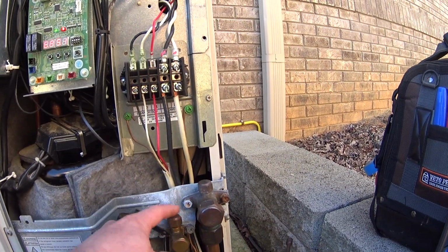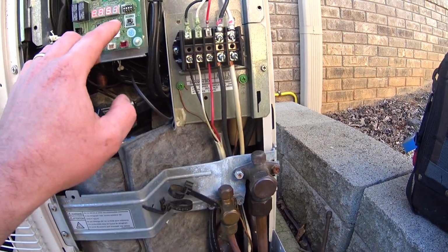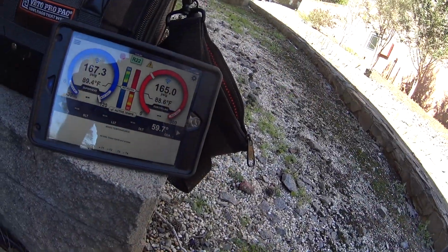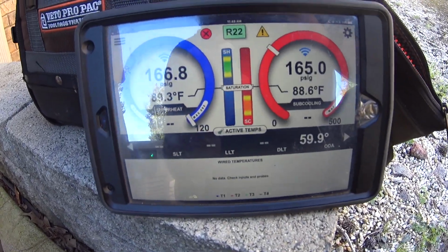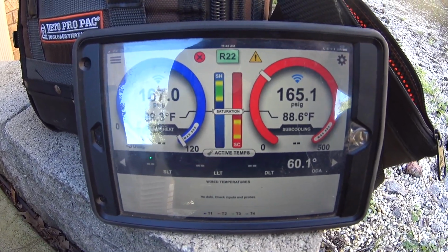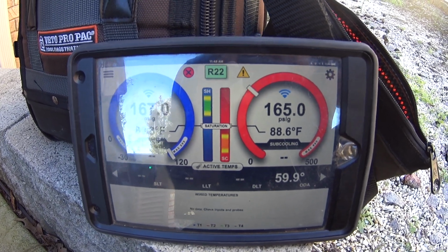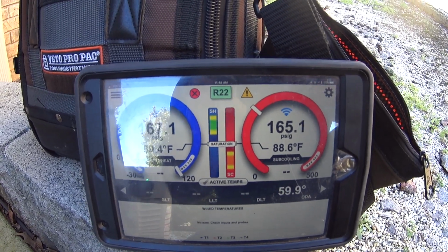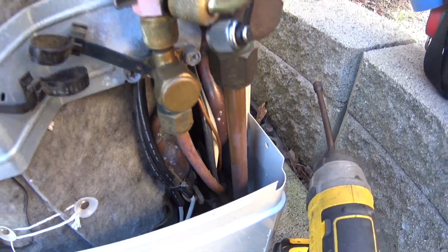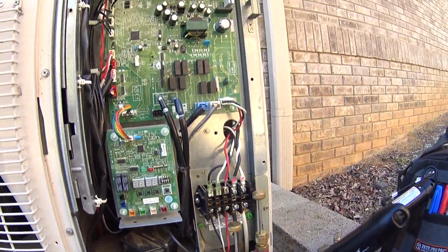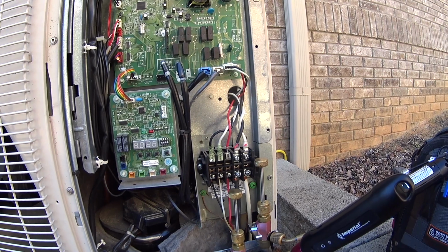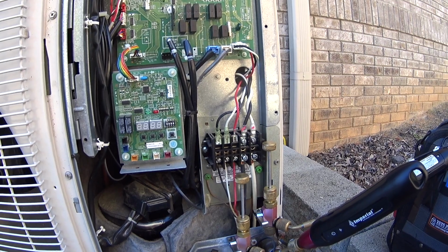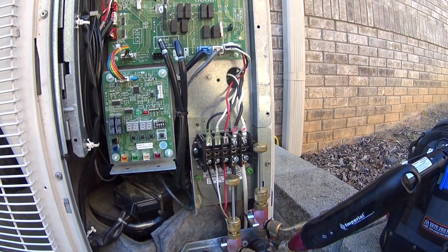I'm going to take the service valve covers off and see what we come up with. So standing pressure looks fine. So obviously, or apparently, it would appear that it is an operational pressure fault. So we're going to see if we can figure that out, find out where the system fails when it runs, and then look at resolving the leak or pressure fault.